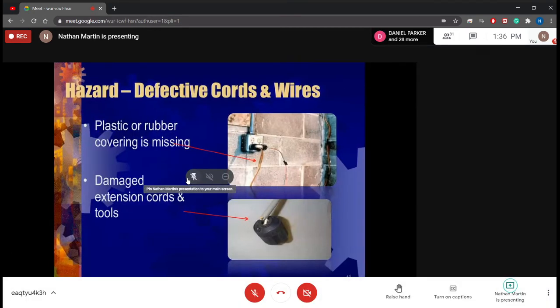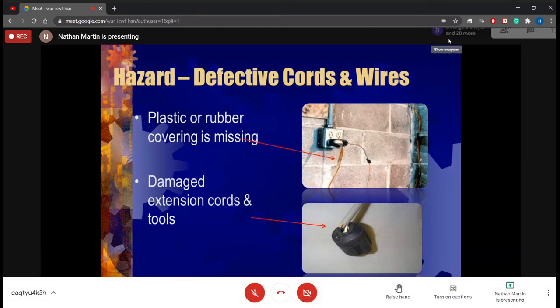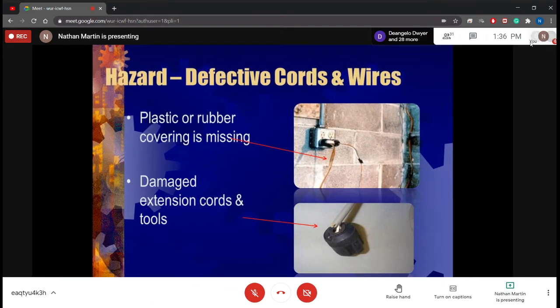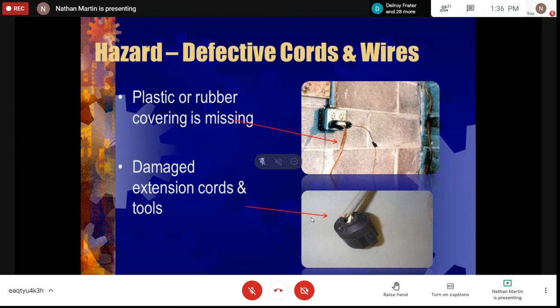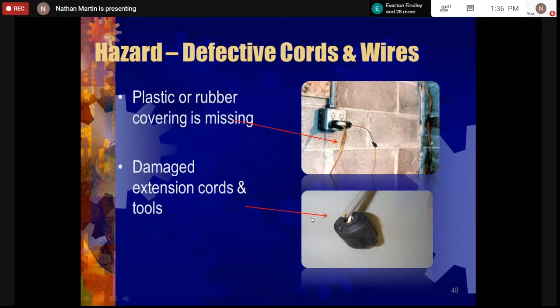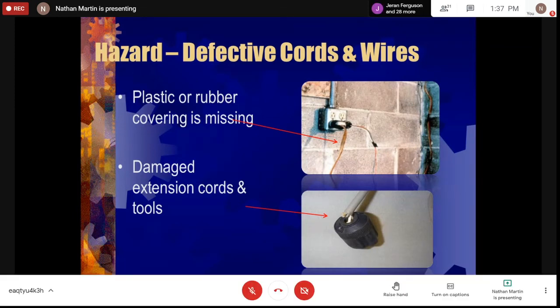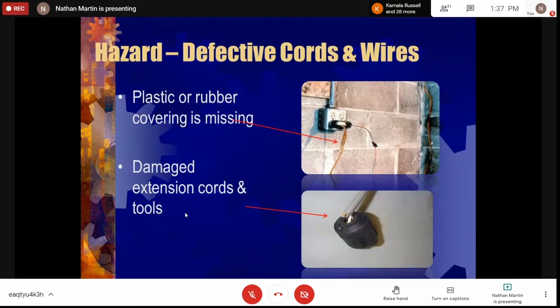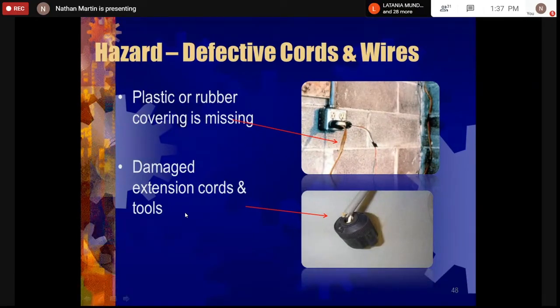So we have another hazard we're showing here - extension cords. This one is very typical in a residential setting, even your work tools. Sometimes your extension cord builds damage after a period of use, where the connection starts to damage and the insulation comes off. You need to re-terminate the cable. Every time I buy the flimsy extension cords, they tend to burn up when you run too much current through them. So I tend to buy flexible cord - that gray cable in the lower picture - and build my own extension. It works out much better.